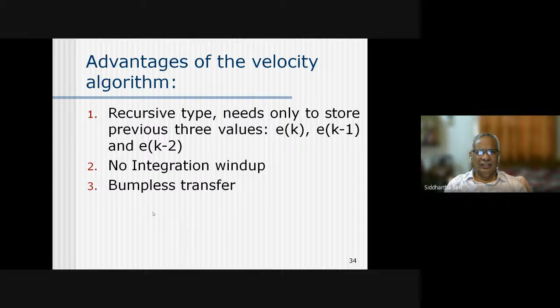This PID controller, while you try to implement, has got 2 difficulties: while you transfer it from auto to manual mode, or there is a sudden change in the set point, there is a possibility of instability or a big jump in the output. One is called integration wind up, the other is bumpless transfer. If we employ this velocity algorithm, these 2 things can be avoided.